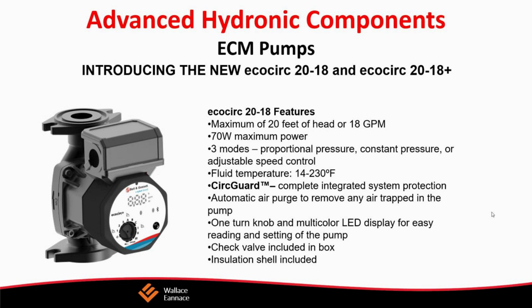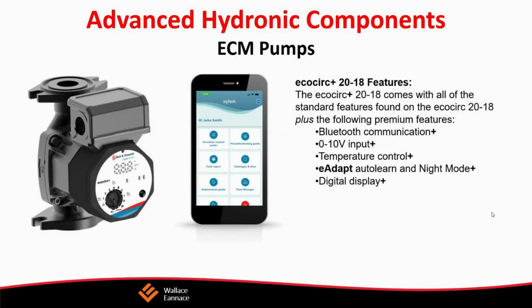There are 3 operating modes. We can set it for proportional pressure. What proportional pressure does is, let's assume we have a system where we have, for example, Danfoss valves. As those valves open and close, the required pressure in the system will change. As the pressure changes, the speed of the pump will change. If the pressure decreases, the speed of the pump will drop. It'll maintain the flow proportional to the pressure. That's what proportional pressure is.